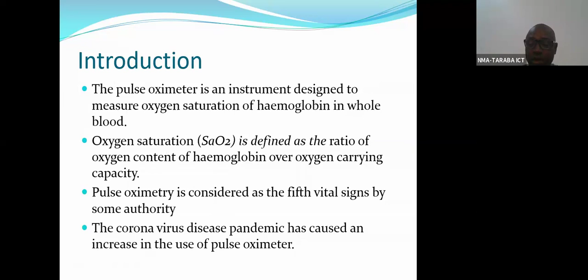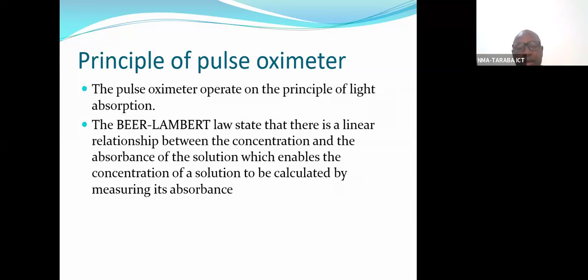So what is the principle by which this pulse oximeter acts? The pulse oximeter operates on the principle of light absorption, that is, using the Beer-Lambert law, which states that there is a linear relationship between the concentration and the absorbance of the solution, which enables the concentration of the solution to be calculated by measuring its absorbance.